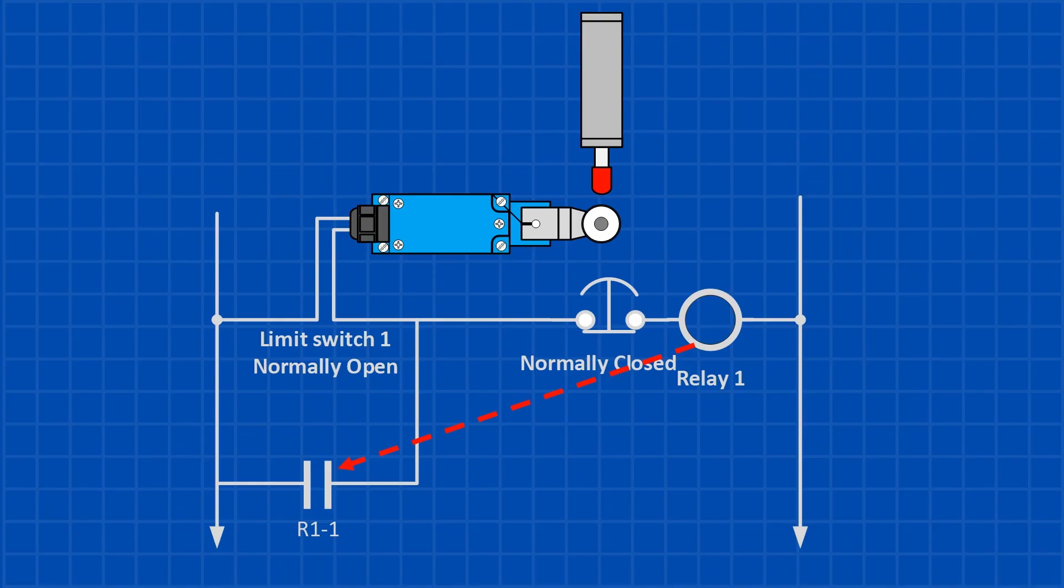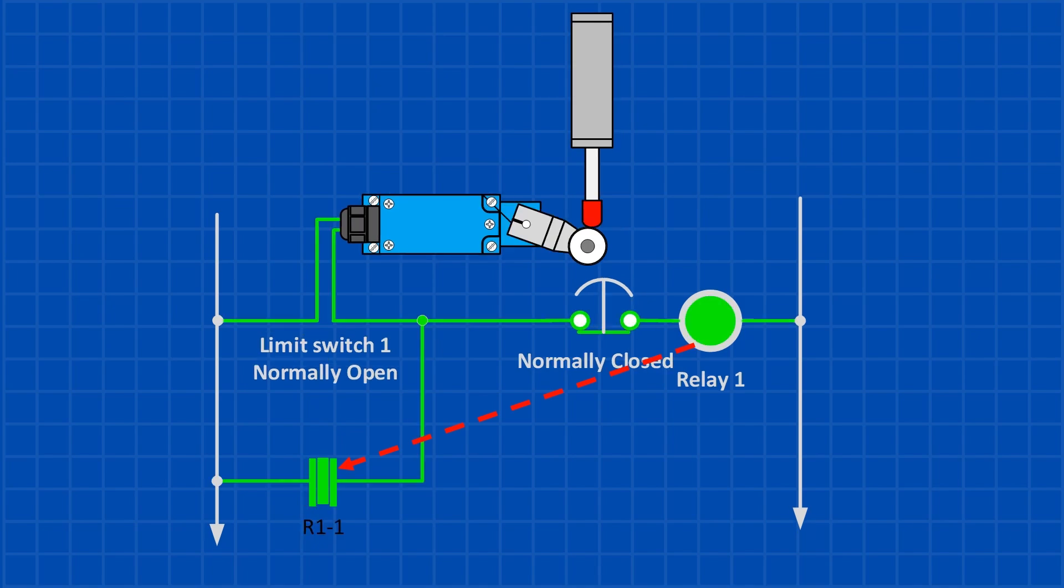Another use for a latching circuit is when you have a momentary signal that only lasts a few seconds but need the output to stay energized longer. For example, a limit switch might only activate for a moment, or an instrument might send a brief temperature spike signal, but you still need to latch an alarm or hold that signal for action. There are many other applications, but these are just a couple of common examples.